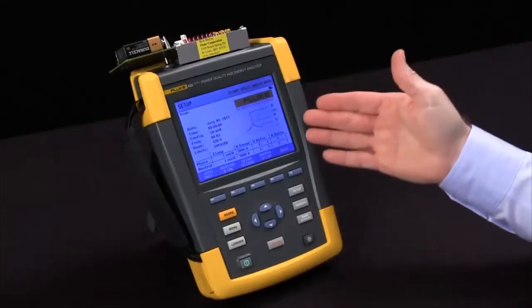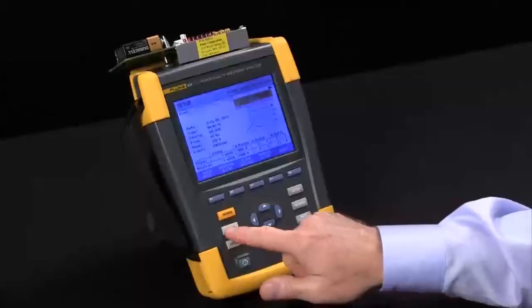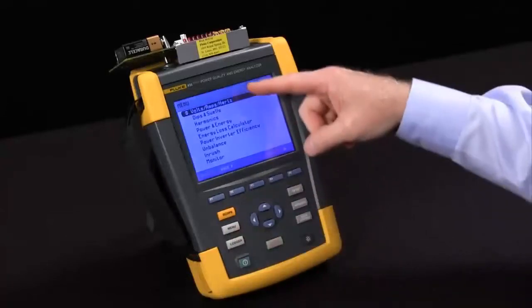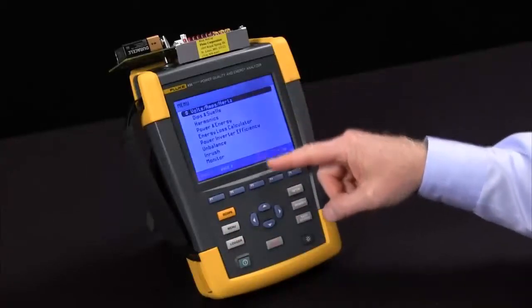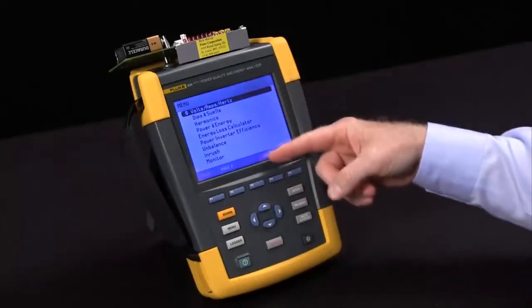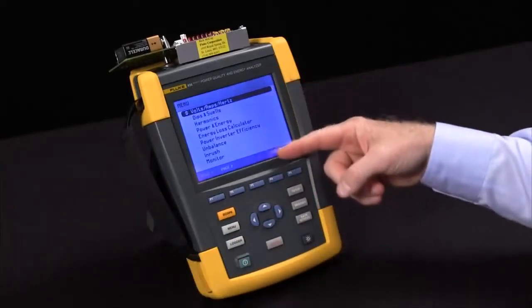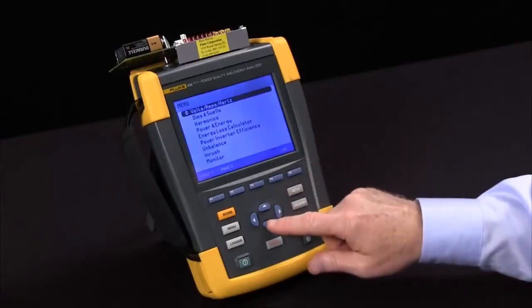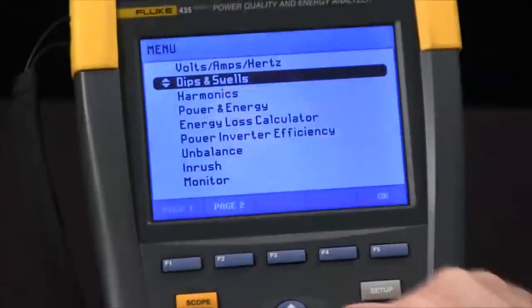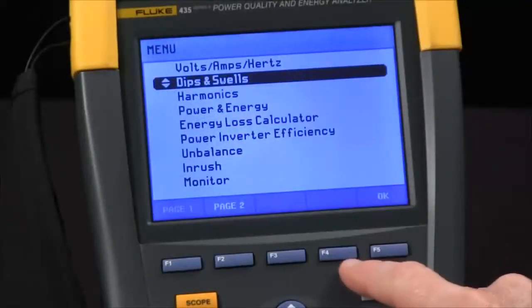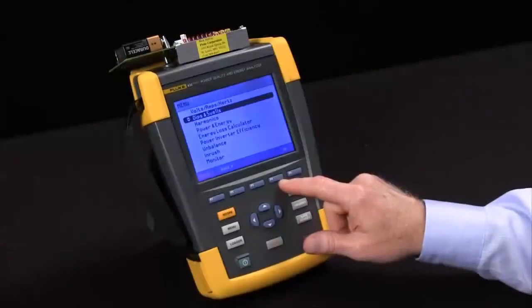In this video, we're going to cover how to set up the Fluke 435 for trending. We'll hit our menu to see all of our tests. The 435 trends for all these tests at a rate of 5 readings per second, with the exception of dips and swells where we do 120 readings per second to give you half-cycle resolution.